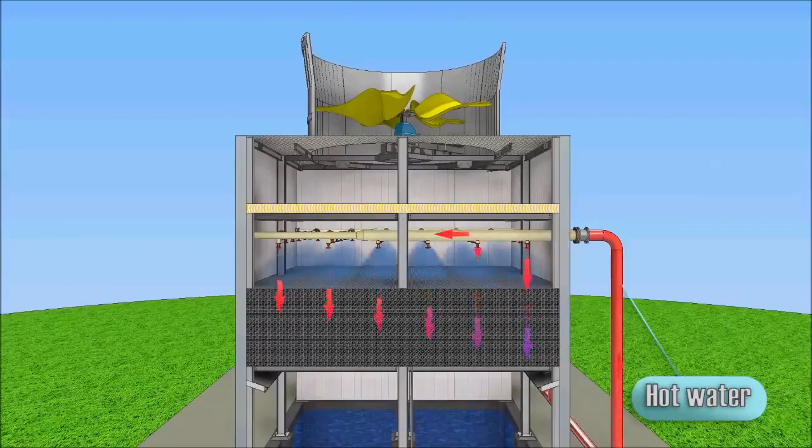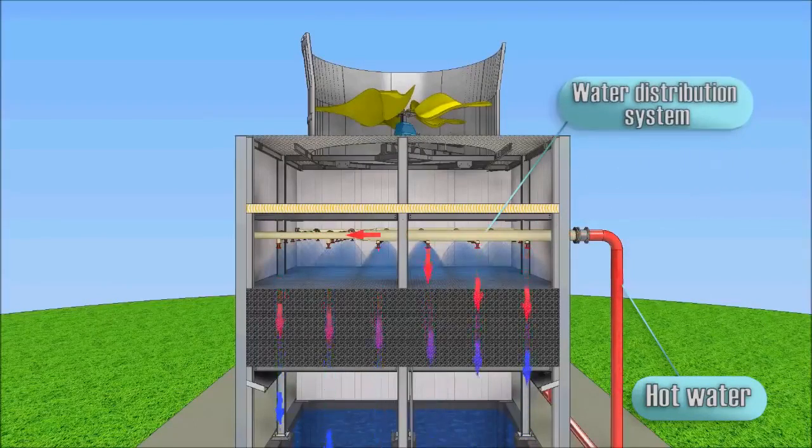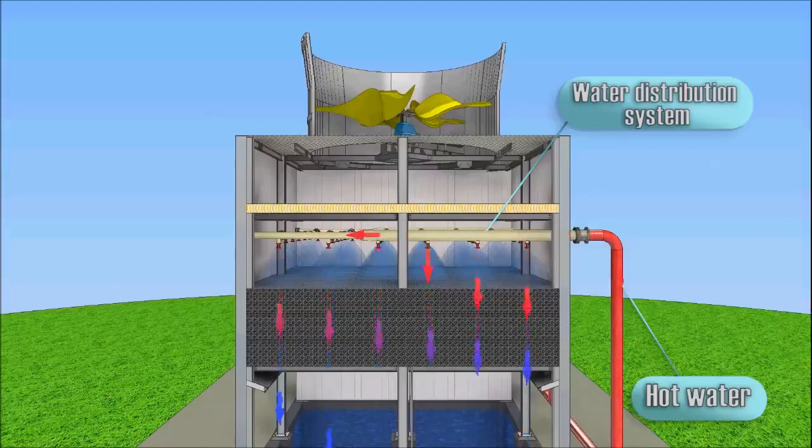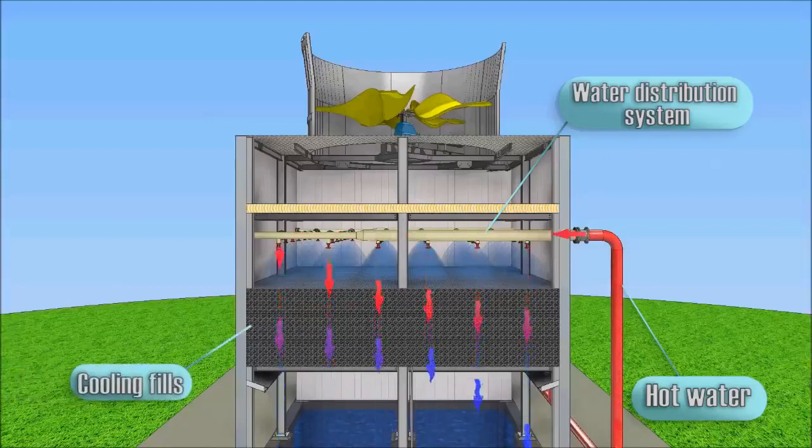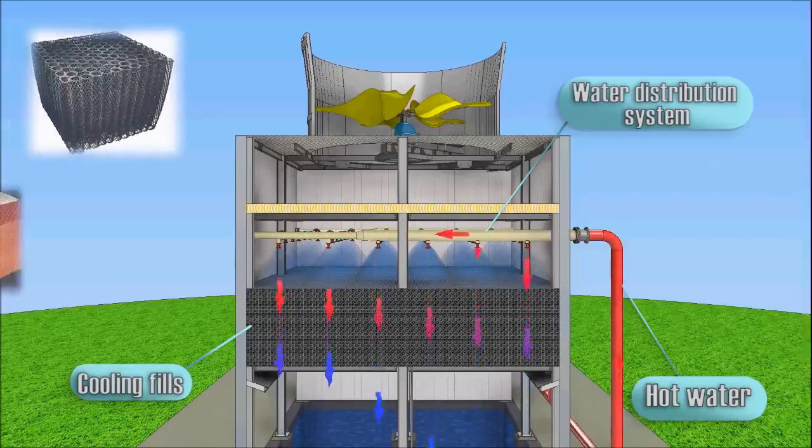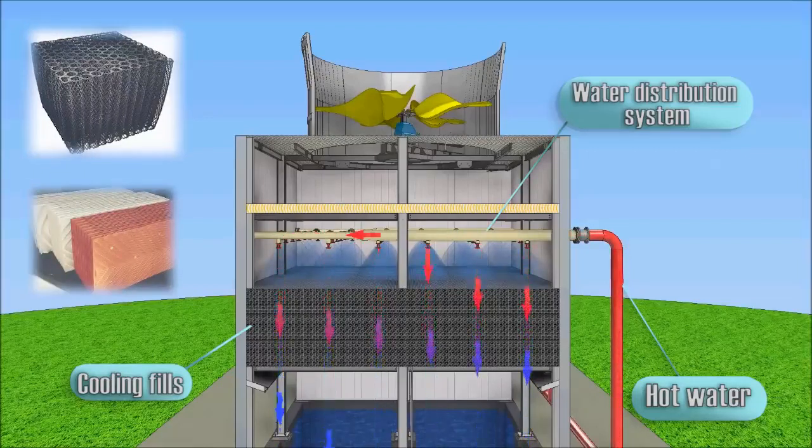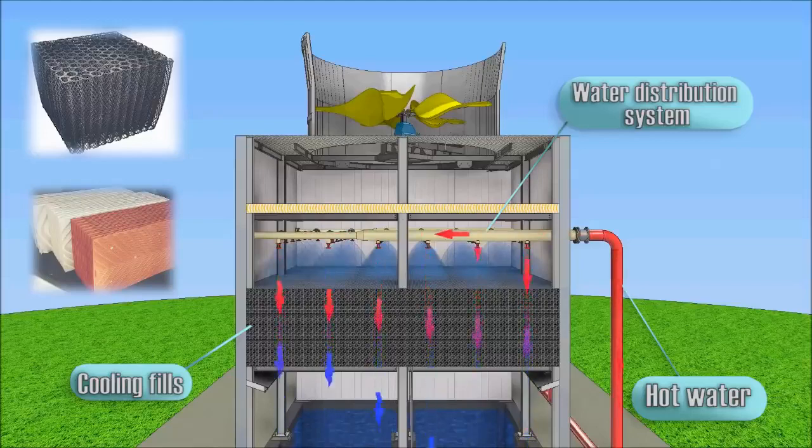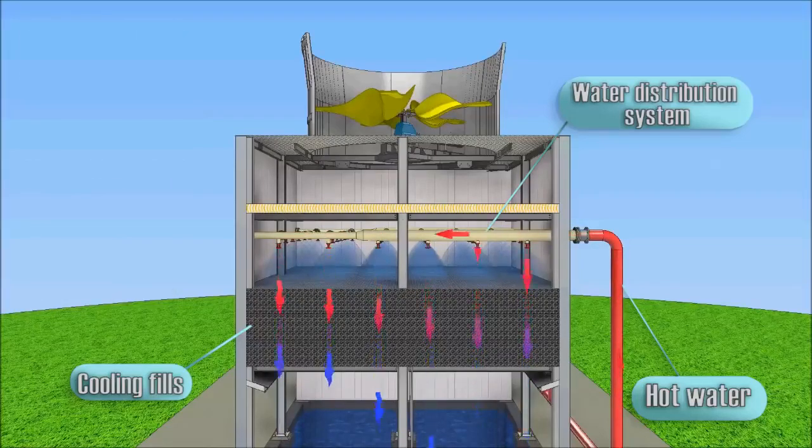Hot water from various sources such as machines or heating processes flows through pipes to the distribution system of the cooling tower, which produces even water distribution to all the area of fills by the spray nozzles. On the fills, the water film is formed from the surface of which evaporation of the water encounters air flow.